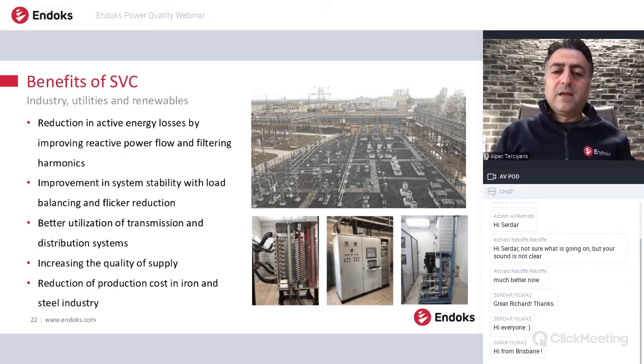And also it balances the system voltage. It is very important because if there is a heavy load having inductive reactive power on this part, and if you don't compensate this inductive reactive power, this heavy load, there will be a voltage drop, and this voltage drop will result in low power transfer from grid to the load. Especially in iron and steel industry, in arc furnaces, it is very important.